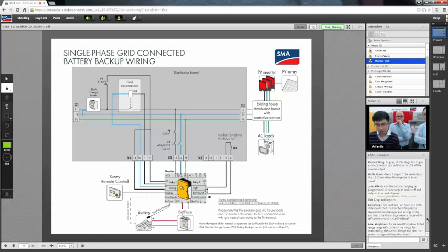You can see that relay 1, in the on-grid backup mode, is already being used. There's one thing that is free - relay 2 is free. So you can potentially add one extra relay here and connect to relay 2. For those that understood the Sunny Island, you can program the relay on time, on state of charge, and other things. So even though the grid is restored, Q2 is closed, you can still use relay 2 to trick the system not to connect to the grid, maybe on time.